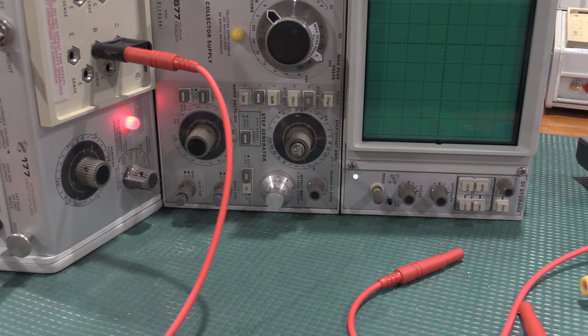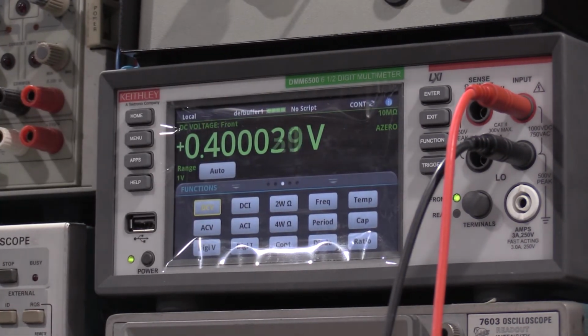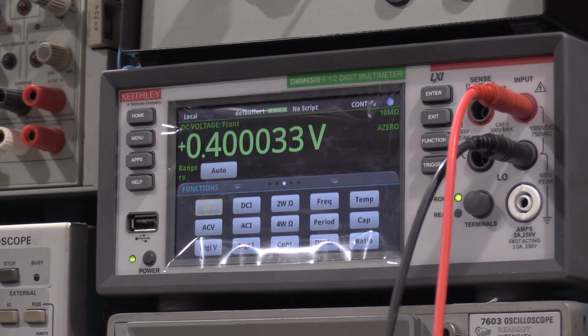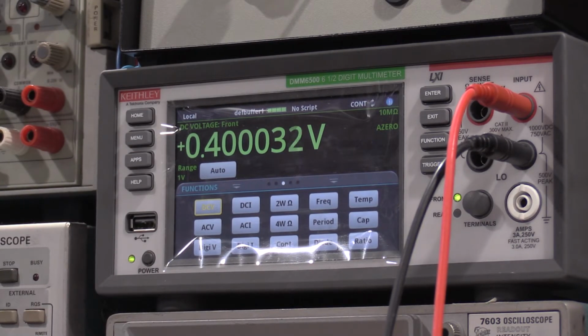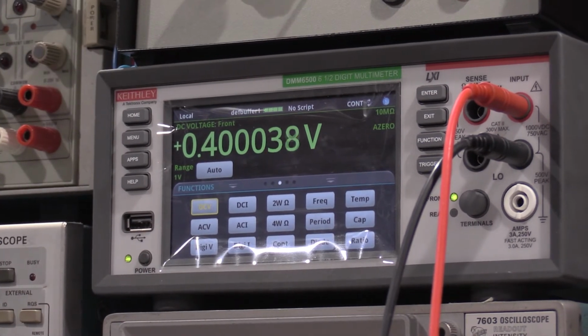So I need to, that did not affect the vertical preamplifier though, so we don't need to redo that. It did affect this one, so now I need to do this, the vertical gain. We have 0.4 volts, 400 millivolts on the curve tracer, or on the DMM. I need to move that to one of the pins on the inside of the collector supply.